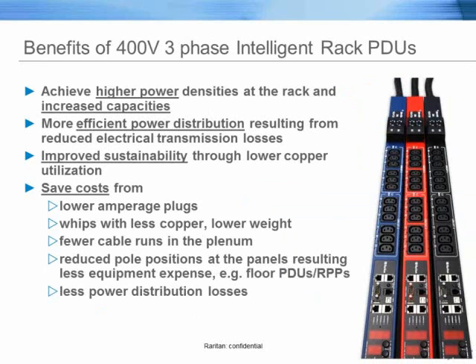So I'd like to review the benefits of 400-volt 3-phase. You're going to be able to increase higher power densities. With that, with more power, you have increased capacities. Now you know how much power you have at that rack, and where we can deploy additional product out there. It is efficient power distribution. By removing that transformer, we're removing a source of heat out of the data center, and we're also reducing additional electric transmission costs. Again, this is a cost-saving factor.